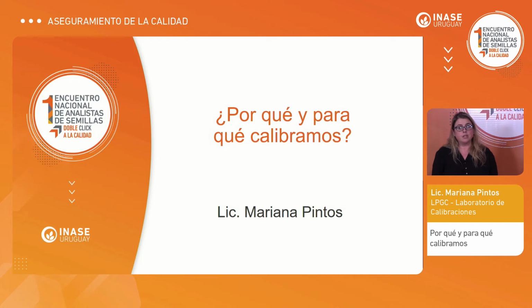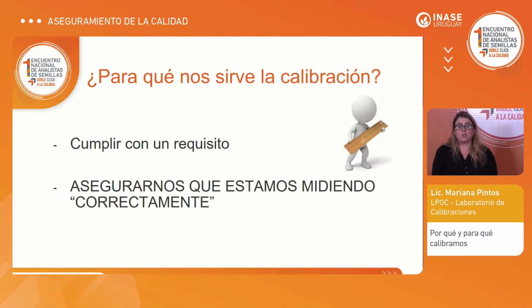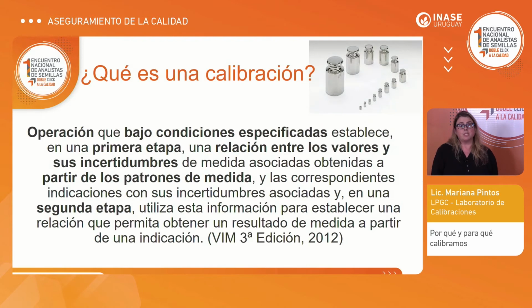As Vanessa was saying, we are a calibration lab. We are accredited by the Uruguayan agency based on this 17025 that came up in the former question. So what we are going to see in this presentation is why and what for is calibration. Most of the people, when they are asked about calibration, say that it is to meet a requirement. It could be a legal requirement, a regulation, or because the audit is demanding that, or some equipment, or everything calibrated. But in fact, what we should care about calibration is that we are sure that we are measuring correctly.